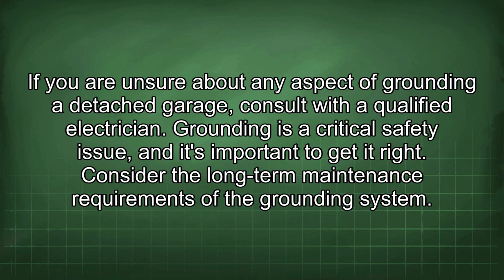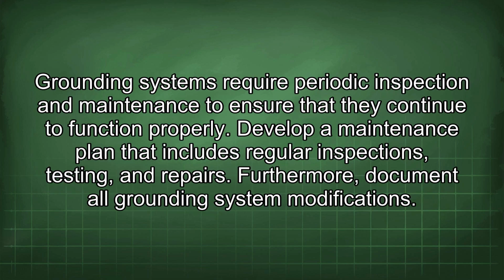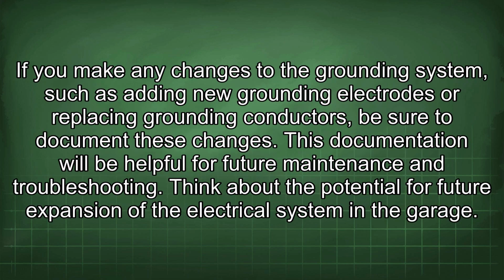Consider the long-term maintenance requirements of the grounding system. Grounding systems require periodic inspection and maintenance to ensure that they continue to function properly. Develop a maintenance plan that includes regular inspections, testing, and repairs. Furthermore, document all grounding system modifications. If you make any changes to the grounding system, such as adding new grounding electrodes or replacing grounding conductors, be sure to document these changes. This documentation will be helpful for future maintenance and troubleshooting.